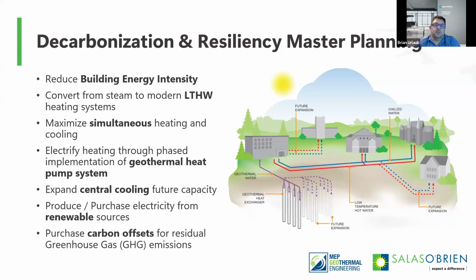When we design a geothermal system, we never really get below 30 degrees on our ground loop. Even in the middle of winter on the coldest week, you're pulling all that heat out of the ground. The fluid will get down to 30. The ground itself is 50. It's still moving heat, and it'll be able to sustain that heat transfer rate to keep it running. And you're not going to dip below 30, which means your efficiencies stay at 3 COP or above.